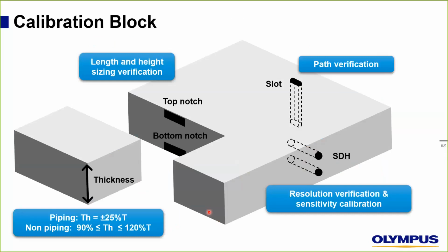First of all, let's have a look at the calibration block dedicated for TFM. It has to include a slot to make the path verification, and SDH to do resolution verification and sensitivity calibration. Of course, here the placement of SDH is not really correct, it's just a representation. Length and height and sizing verification, in other words, should be done using top notch and bottom notch, or sometimes just top notch and you flip the block and you do it on the other side.